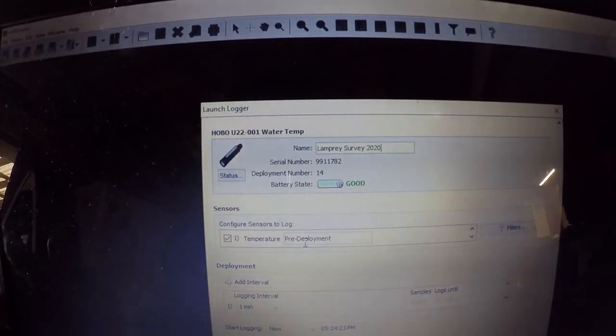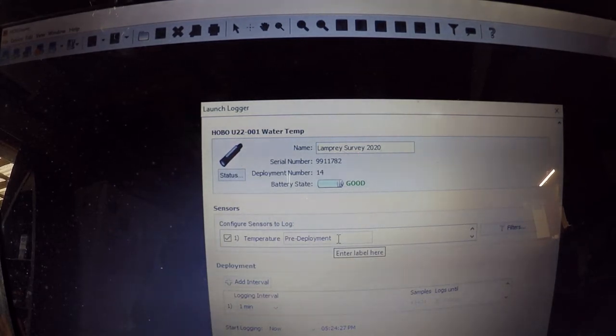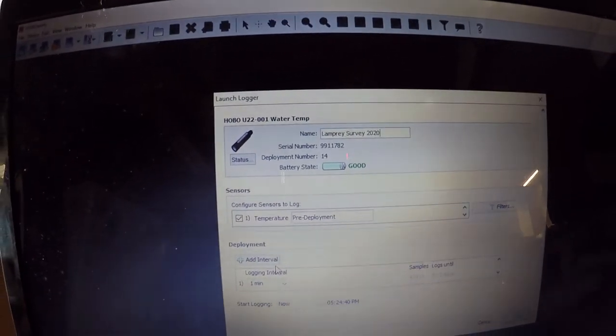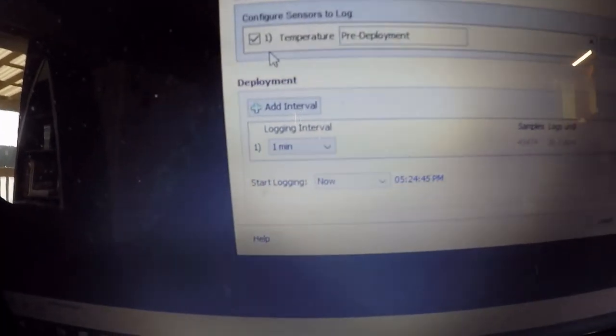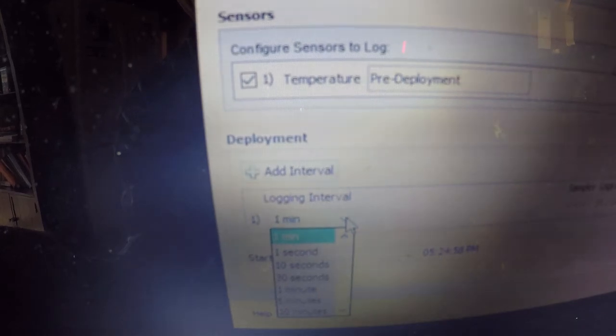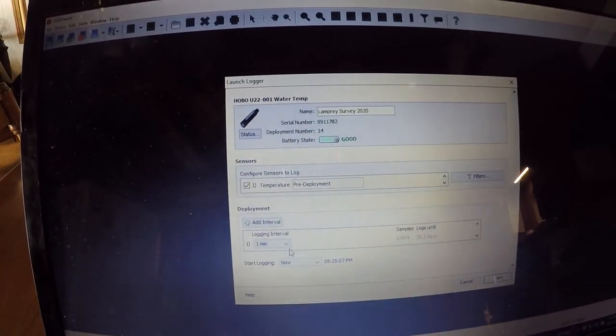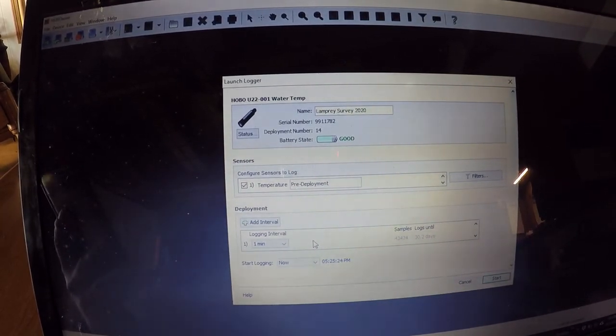Right down here it says temperature and pre-deployment. So that means this is what we're using this for, the pre-deployment check. So we're going to just leave that at pre-deployment. If you go down one more step, and let's see if I can get you to see this, and it's not the greatest, but basically this says logging interval, and right under here it gives you a drop-down box that allows you to pick different times, and we're going to put 1 minute for that. The reason that we're picking 1 minute is because we're doing the calibration at this point, and we want to be able to get a reading every 1 minute so that we can tell when to put our manual thermometer in and take a reading.